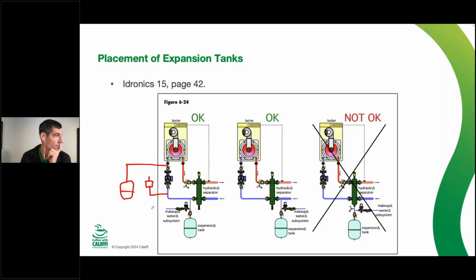You probably don't have it in the stack of slides, that shows the relationship of the pump and how it changes that. I think it's in three or four of our hydronics presentations that we use that Bell and Gossett example, because it is a really good example of how the relationship of the expansion tank to the circulator determines what the pressure is throughout the system. If you put a gauge all throughout your building, you can see the pressure change based on the pumping relationship.